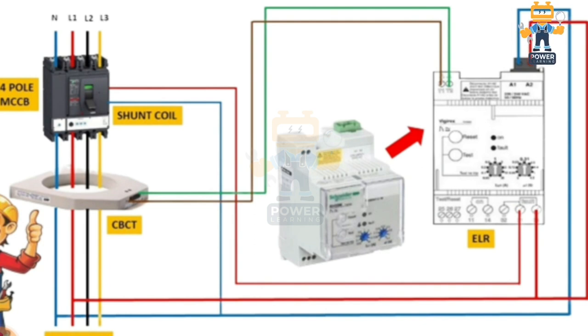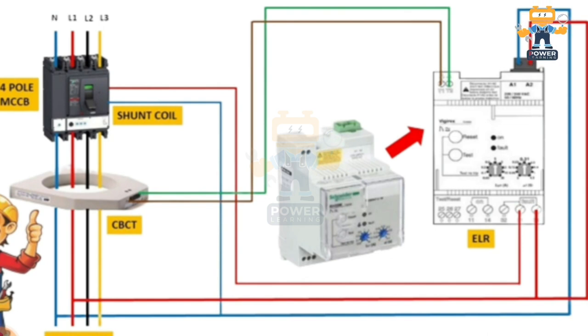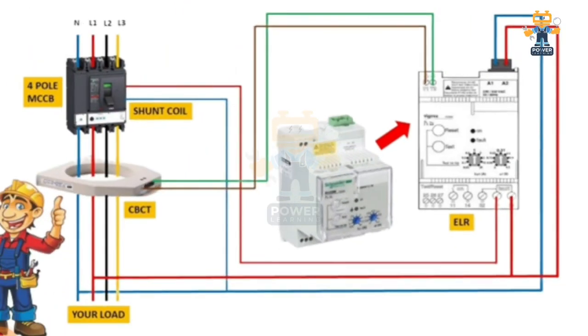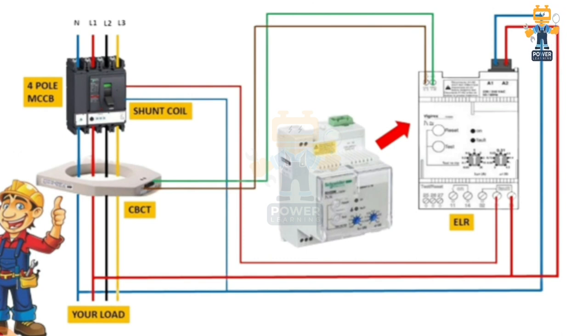Next, we take two wires — one neutral and one phase wire — and connect them to power up our earth leakage relay. The power terminals on the earth leakage relay are A1 and A2. We took these two wires from the load side and connected them directly into A1 and A2, so the earth leakage relay is now powered up.